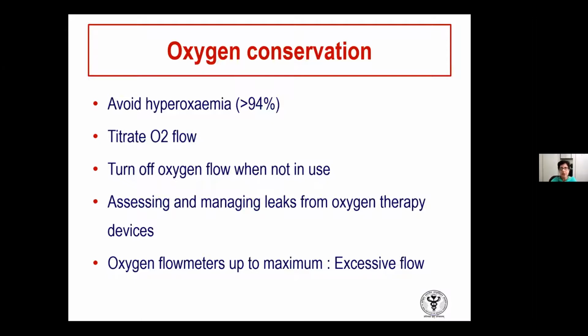One should ensure that all oxygen flow has been turned off. Say the patient wants to eat or drink and has removed the mask for some time, quickly turn off the oxygen, because you're wasting the oxygen during that time. So one should turn off oxygen flow, even remove oxygen flow meters from the wall outlets, because sometimes when you keep the oxygen flow meters in the wall outlet, there might be some leak around the flow meters as well.